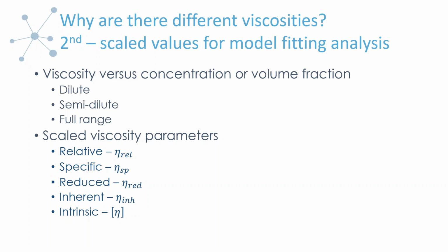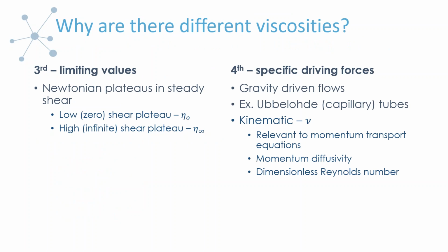And just to point out now another reason why we wanted to do this type of webinar: we've had some customers or potential customers who somewhere got misled along the way, not realizing that these are all actually calculated from the steady shear viscosity. They didn't realize that you didn't need a special type of instrumentation to get these values. You just needed to be able to measure steady shear viscosity and know certain things about your sample, like the concentration or volume fraction, and then you could calculate them.